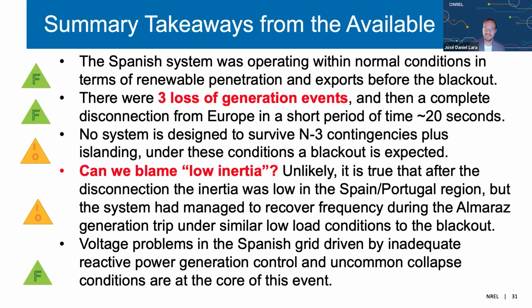Some of the takeaways from the available data are that the system was operating within normal conditions in terms of renewable penetration and exports. It wasn't exporting more than normal, it wasn't producing more than normal. There were 3 loss of generation events and a complete disconnection from Europe in 20 seconds. It is no surprise that a system that has to go through these N-3 contingencies plus islanding goes into a blackout. In 20 seconds, an operator cannot actually perform maneuvers to save the system from collapsing.